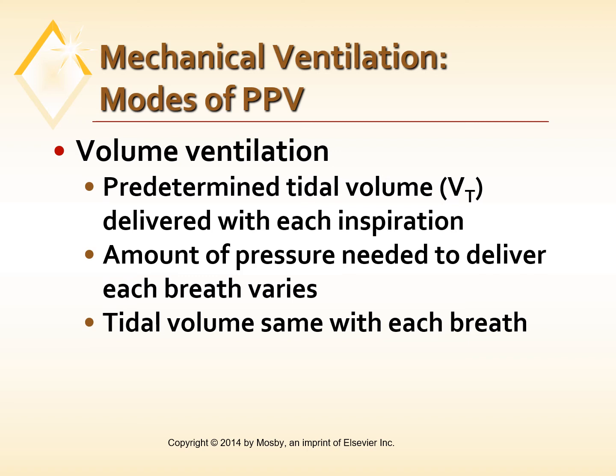So this can be dangerous for patients with really stiff lungs who have a lot of crap in their lungs. It doesn't matter the amount of force that the ventilator will have to use to push air into the lungs to maintain that tidal volume. So we can actually wind up damaging the lungs if we're having to use a lot of pressure to deliver this tidal volume. So this is just one of the modes. It has a set, predetermined tidal volume, and then it depends on the amount of pressure the ventilator sets to achieve the same tidal volume with each breath.